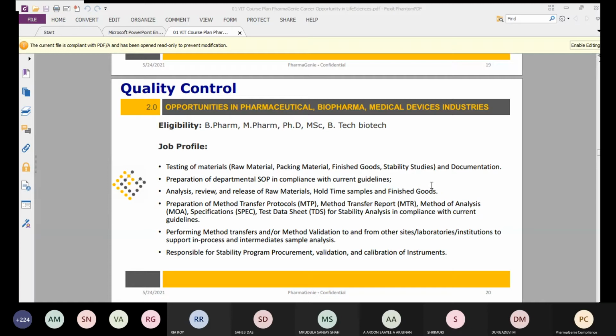So for any instrument, there are four important things. First is the cleaning of the instrument. Your SOP should cover cleaning, how to clean the instrument, how to operate the instrument, how to maintain the instrument, preventive maintenance of the instrument, and how to calibrate. Minimum these 4 parts should be there in each instrument document: cleaning, operation, preventive maintenance or troubleshooting, and then your calibration. This is very important.